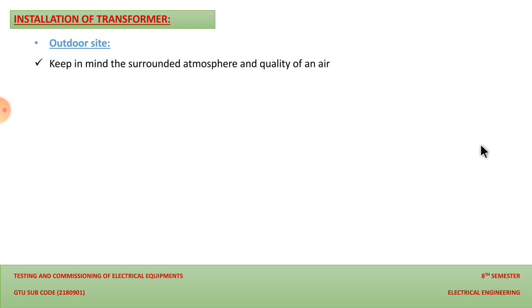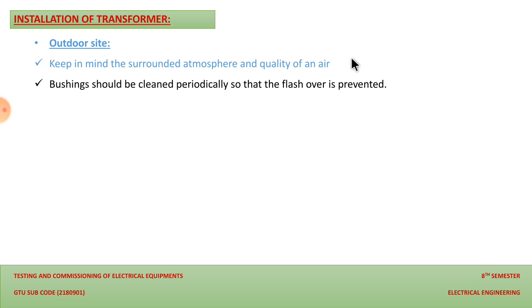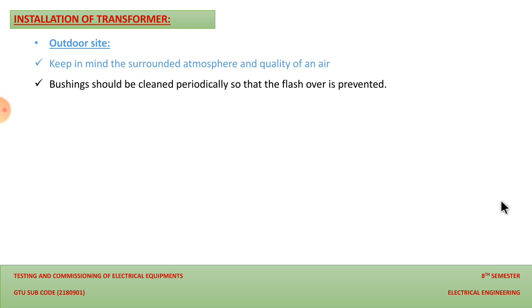Keep in mind the surrounding atmosphere, because the transformer will be highly affected by moisture and contaminated air. So we need to check the quality of the air while installing at an outdoor site. Then the bushing should be cleaned periodically, so that flashover is prevented. Bushings are generally made of porcelain, and if there is contamination on the bushing, then there might be chances of treeing and tracking of the bushing, and the chances of flashover will be more. That's why we have to keep it as clean as possible.